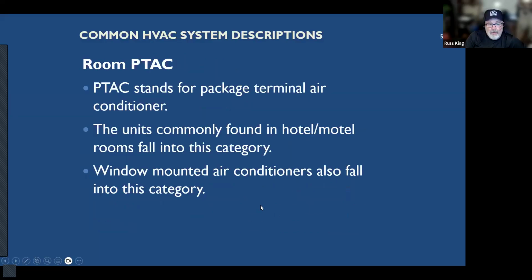Another type of package unit, I'm sure everyone has seen one of these, is what you typically see in a hotel room. When you go into a hotel room, next to the window or under the window is going to be this unit in the wall. That's a package unit because it's all one box. The condenser is outside, everything else is on the inside, but it's one unit. We call it a package terminal air conditioner or a package terminal system. Very common in hotels and motels.